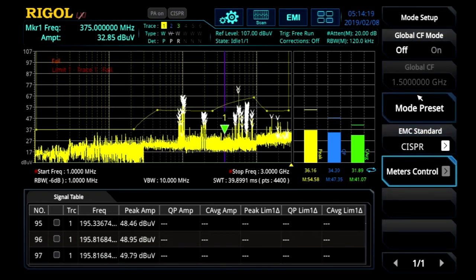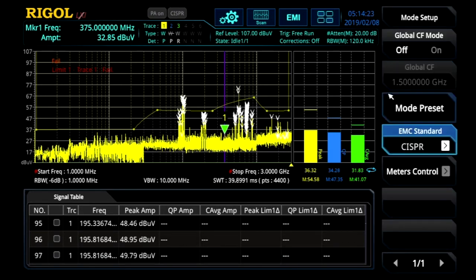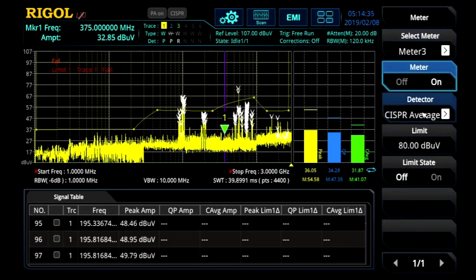Here in the mode setup is one of the first areas we look. You can set CISPR or the regular detectors. Here you can also configure the meters — we've pre-configured them for a peak detector, a quasi-peak detector, and a CISPR average detector. That gives us the ability to look at three different ways these signals might appear in an actual compliance test.